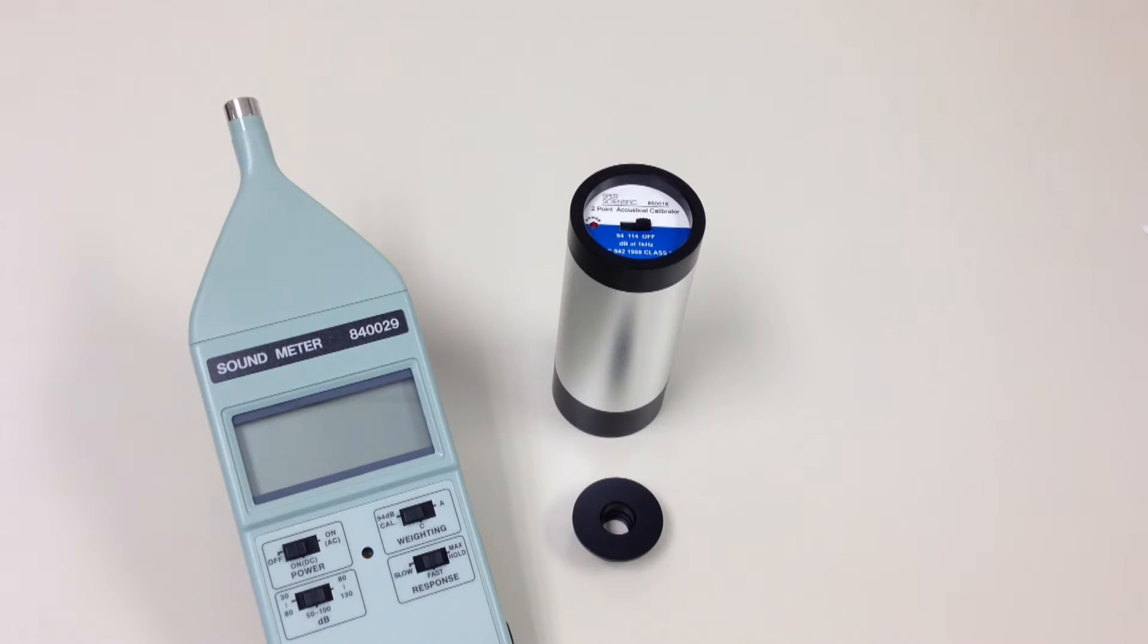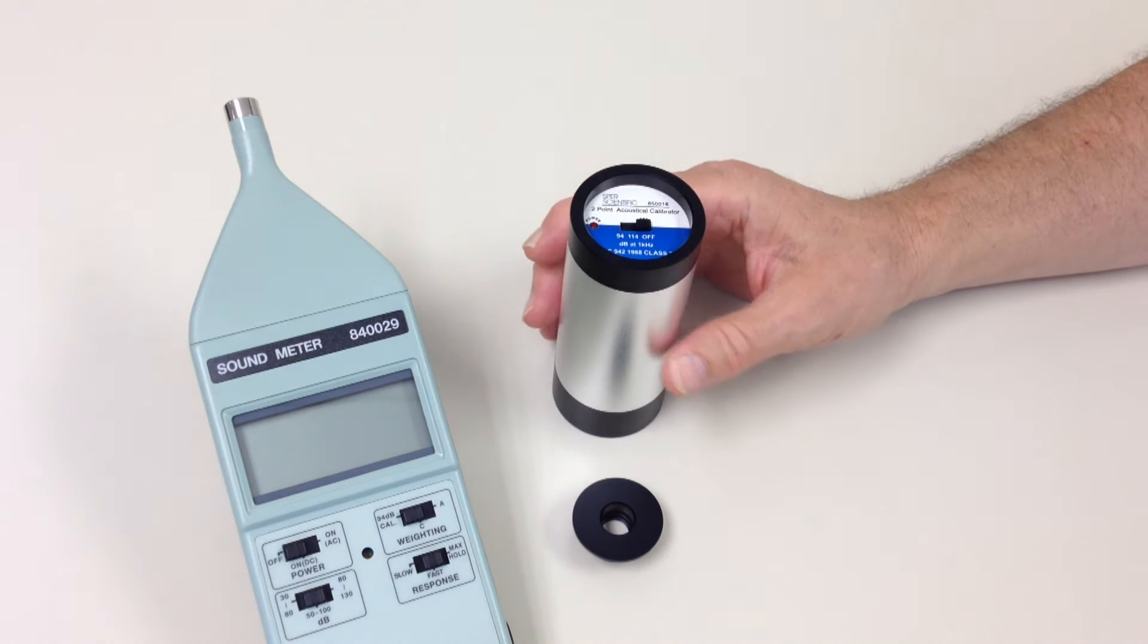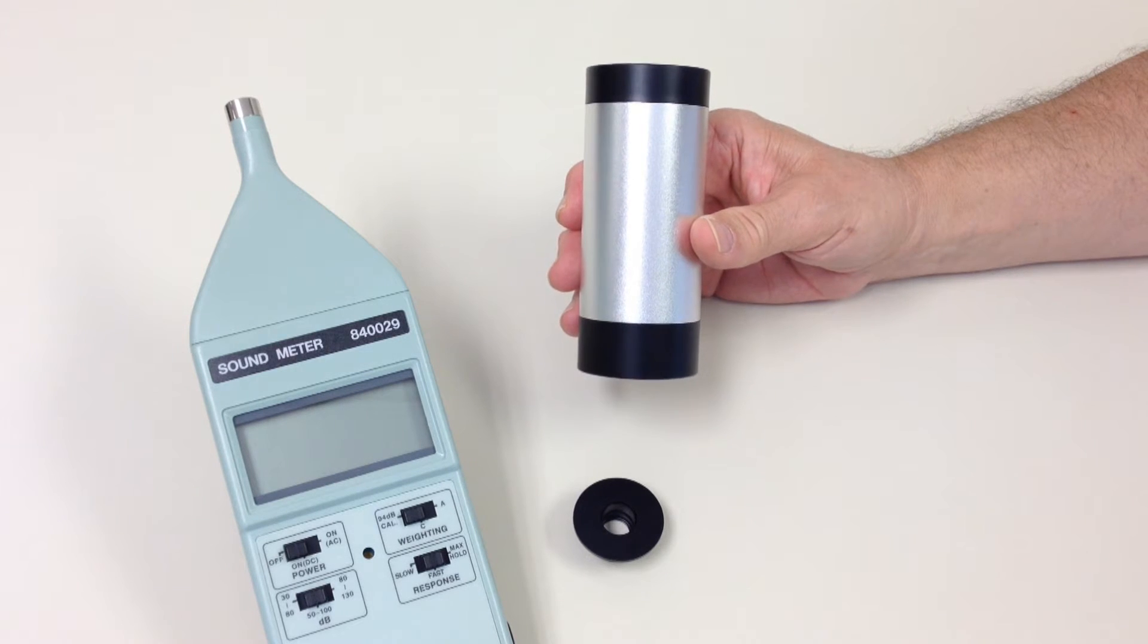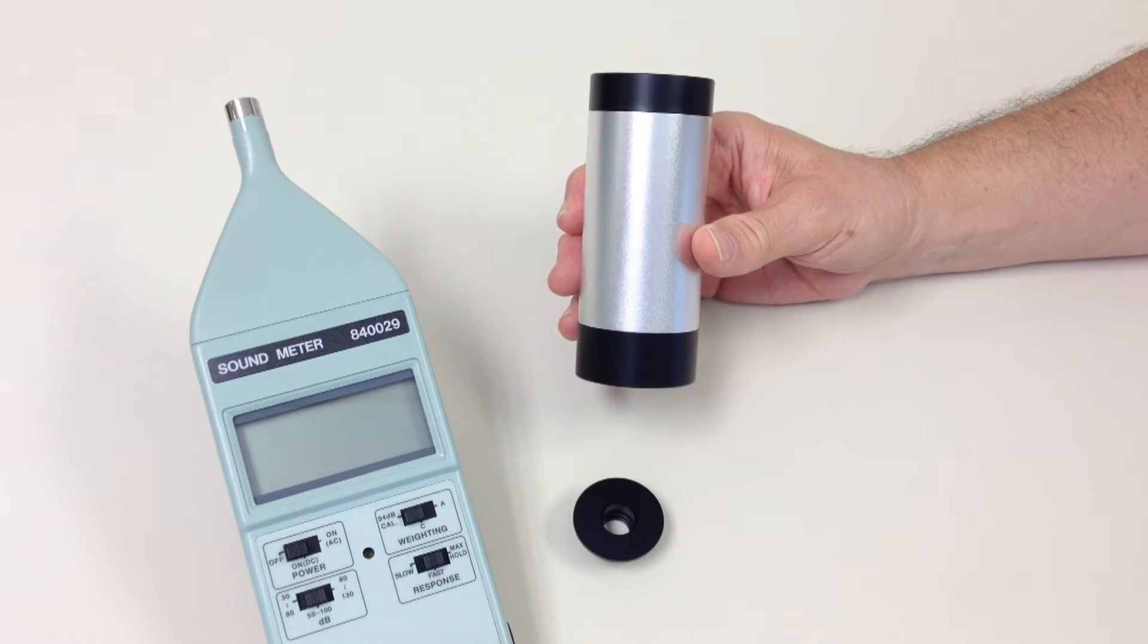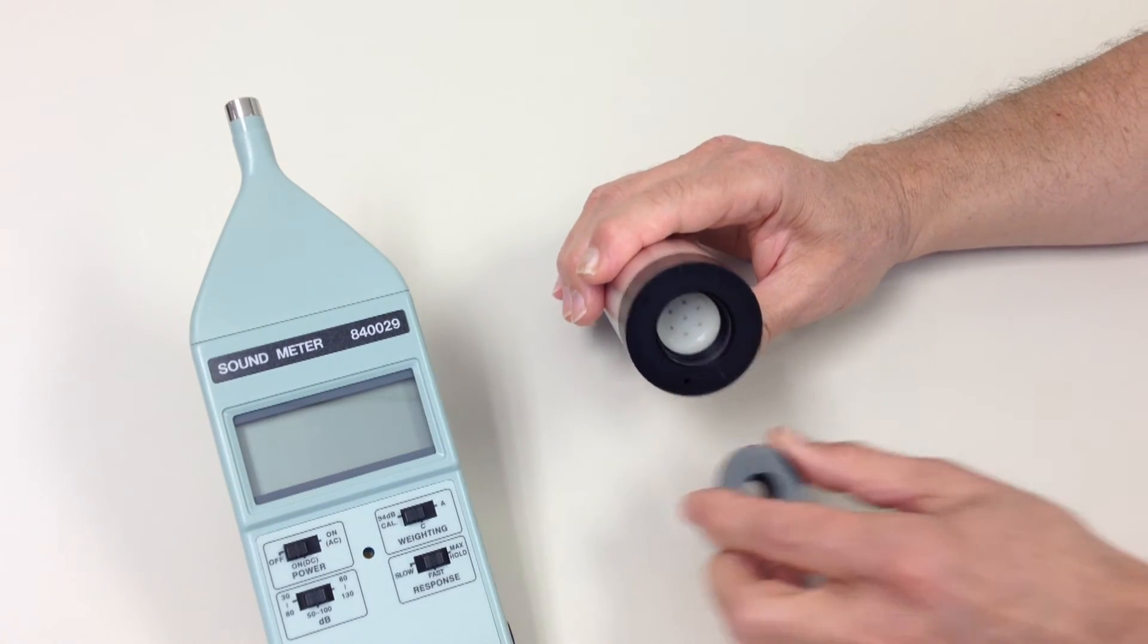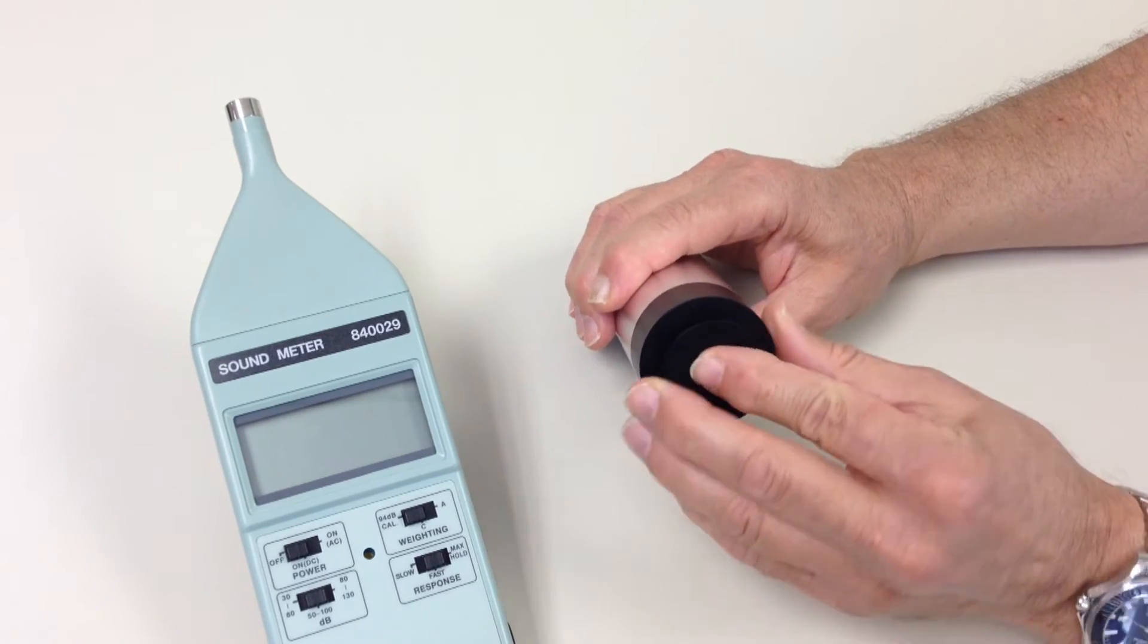In order to adjust the entire system, including the microphone, you need an acoustical calibrator, like Spear Scientific's two-point acoustical calibrator 850016. This model works with any digital sound meter with a one-inch or one-half-inch microphone.